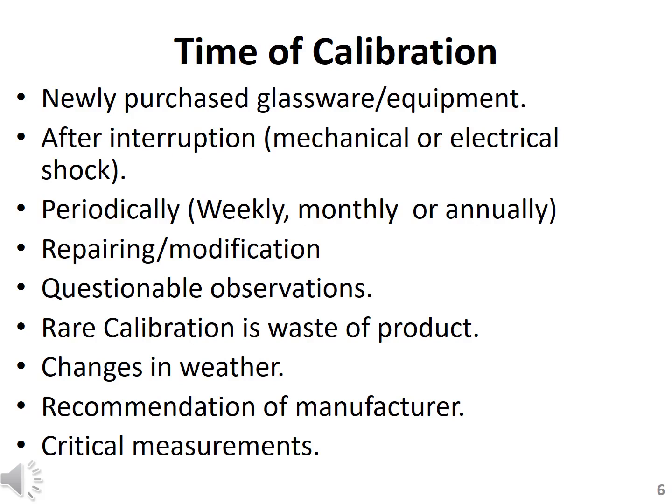The fourth case, in that case we are going to calibrate when the specific uses or operational hours have passed. In that case, we will also be calibrating that equipment or instrument. When you repair or modify the equipment, then you will also be liable to calibrate that equipment or instrument.